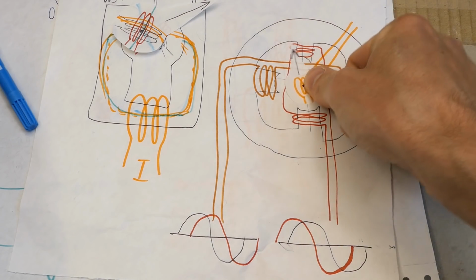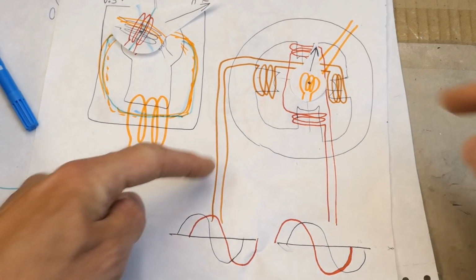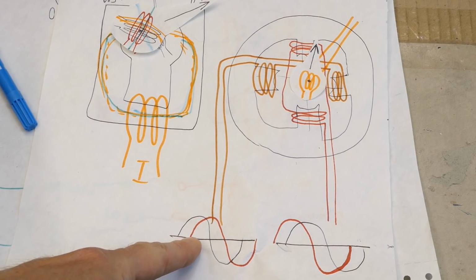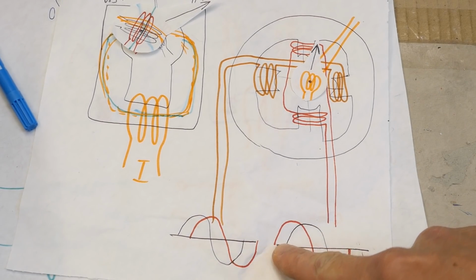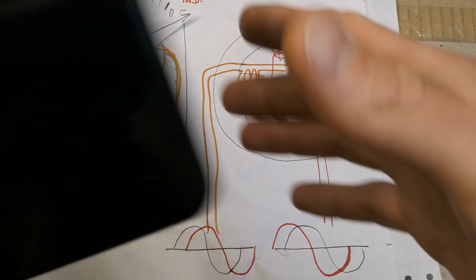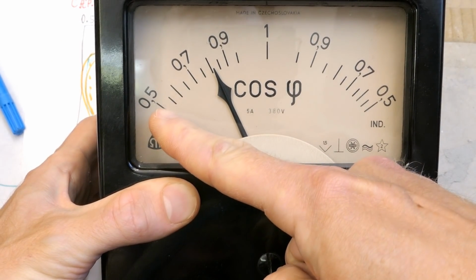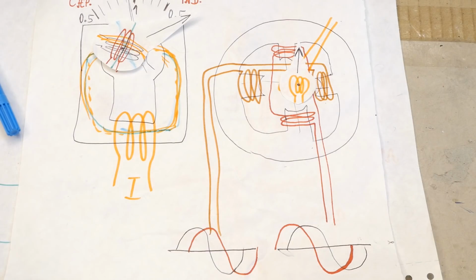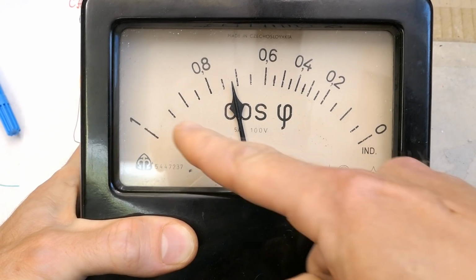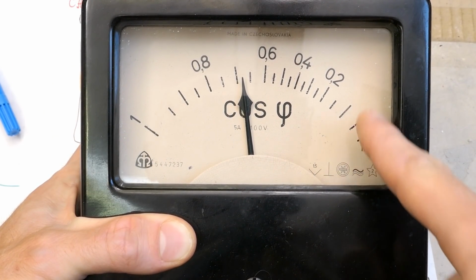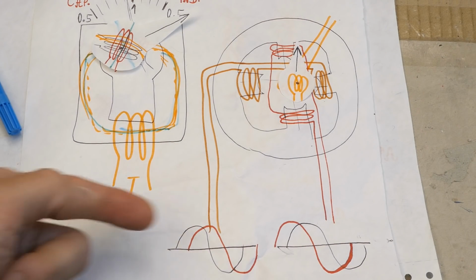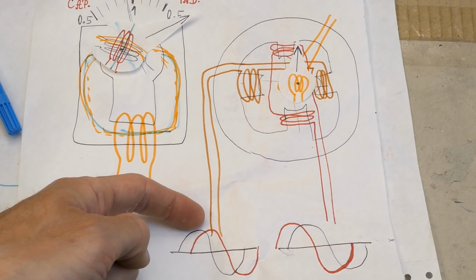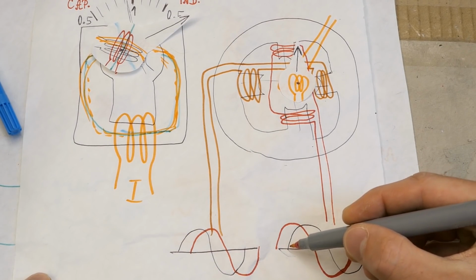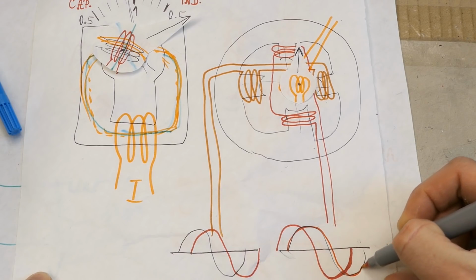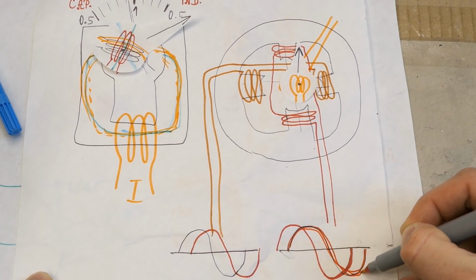This is the current sensing coil and these are the reference coils. One gets a current which is behind the voltage and one gets a current which is ahead of the voltage. And this is true at least for this one which is symmetrical both into capacitive and inductive. It might be a bit different for this one, which only goes to inductive, 0 inductive to 1, and doesn't go to capacitive. In this one maybe one of the coils gets an inductive current which is behind the voltage, and the other one might actually get a resistive current which is in phase with the voltage.